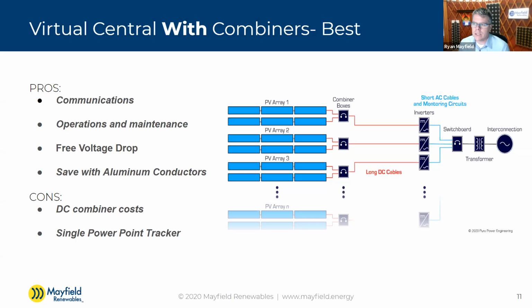So the 90C, I guess, is the question. I would say all of the combiners I've seen are rated for aluminum conductors. 75 versus 90 would be the question on the rating on those terminals. And a big part of that too is what's connected to the terminals. If there are overcurrent devices connected to them, or if they're just straight lugs, that will have a big impact on 90 degrees C versus 75 C. So I wouldn't say assume anything, but I think it would be a safe expectation that you would have at least 75C conductor terminals rated for aluminum conductors.